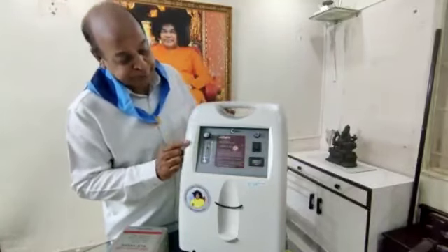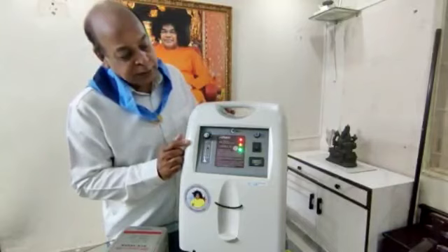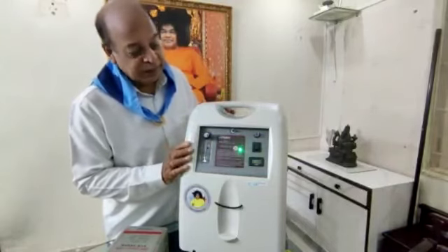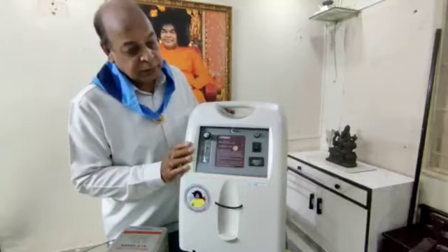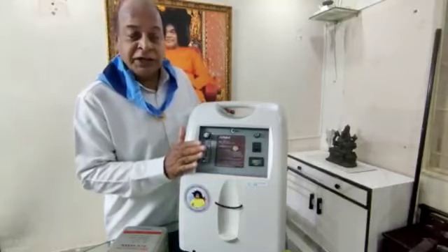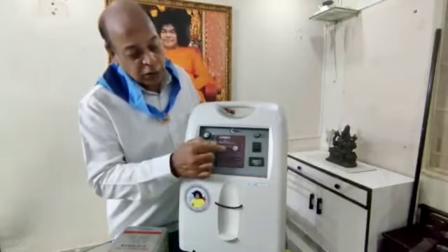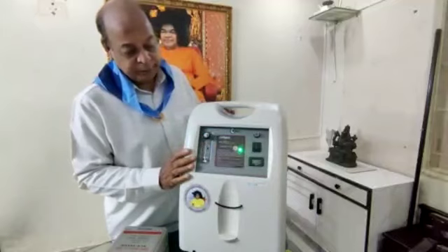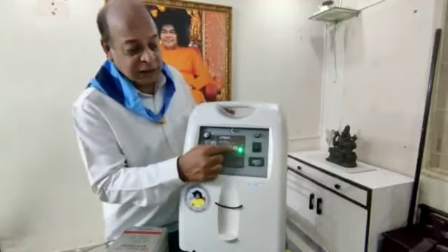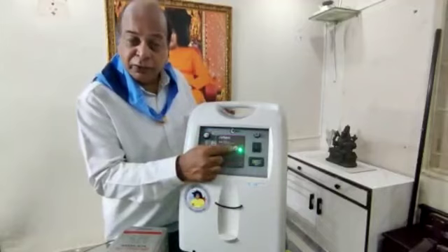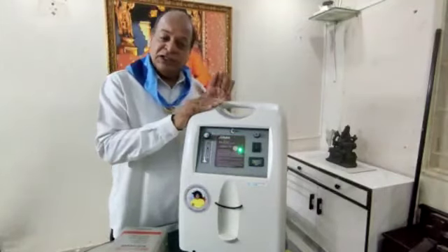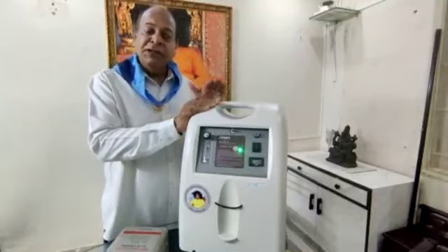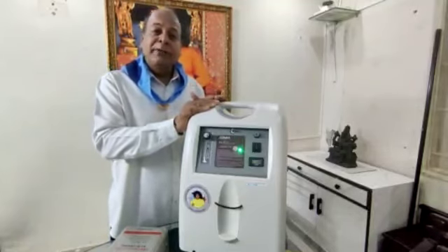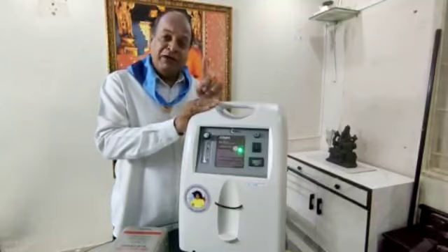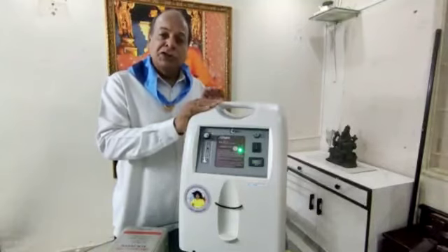Let's wait and watch here. You can see they are blinking right now. The machine is powering up. Once it is ready to use, as I mentioned, it goes on a full green. Right, now we see that the machine is powered up and it is ready for use. This concentrator is a 5 liters per minute. It delivers 5 liters per minute, 90% plus or minus 3 at 5 liters. So there is a stabilized mode of oxygen outflow.